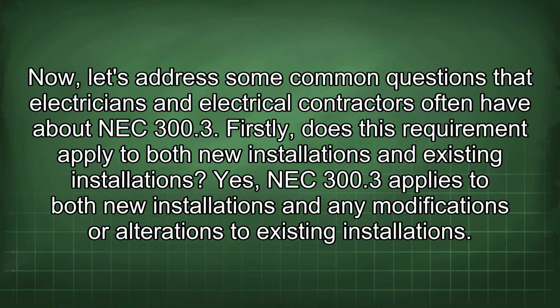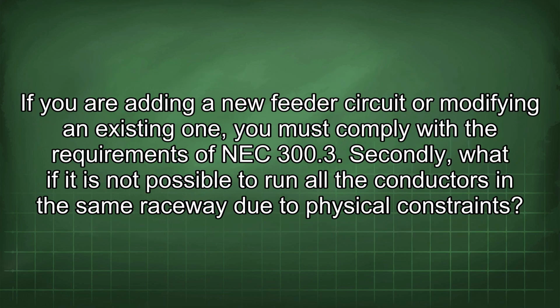Now, let's address some common questions that electricians and electrical contractors often have about NEC 300.3. Firstly, does this requirement apply to both new installations and existing installations? Yes, NEC 300.3 applies to both new installations and any modifications or alterations to existing installations. If you are adding a new feeder circuit or modifying an existing one, you must comply with the requirements of NEC 300.3.